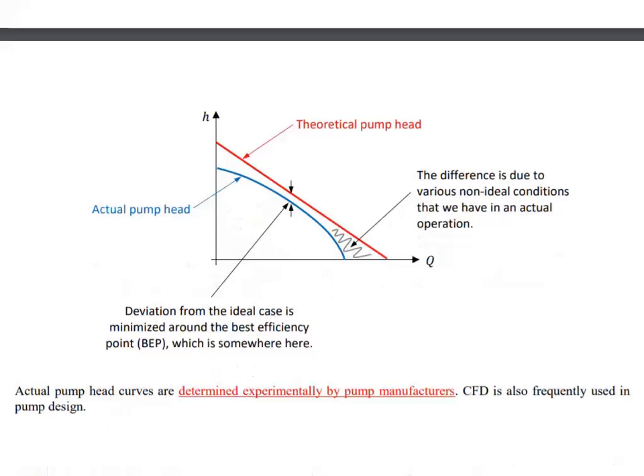The actual H-Q relation is not linear due to the losses and non-ideal working conditions. The blue curve shown is a typical actual H-Q relation of a centrifugal pump. Deviation from the ideal line increases as we go to low and high flow rates. Ideal and actual curves are closest somewhere in between, which is the point where the pump works with maximum efficiency. This is the design point of the pump.